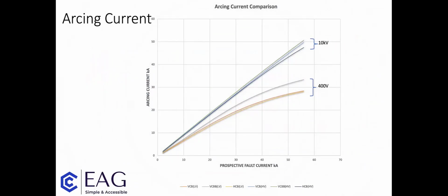So nearly there, and I've finished. But before I do, I realise that there's a good number of you that are responsible for low voltage system design. So I'd like to dedicate this slide to you. If incident energy and arc flash boundaries and so on are a little bit of a yawn to you, I think the calculations just providing information on the value of arcing current is really valuable. I hope it wouldn't come as much of a surprise to find that the arcing current will be lower than the available prospective short circuit current because of the impedance in the arc.